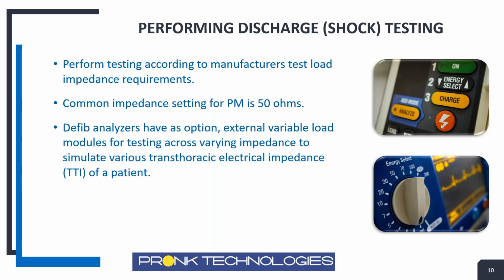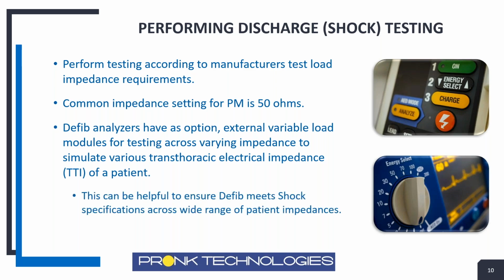The defib analyzers in the marketplace have modules, an extra accessory that allows you to simulate different transthoracic impedances. There's usually a separate module you can connect to it, so you could vary the impedance on the test equipment and check those other impedances. So it's something that could definitely be considered, particularly if you're investigating an incident. It could be a good test to do, to see whether it works across those impedance ranges.